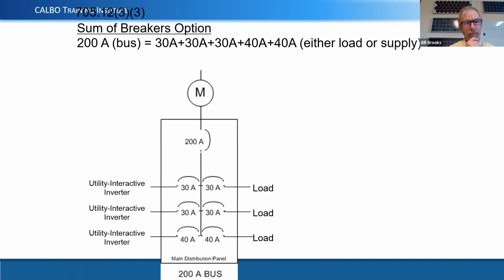Now, it's challenging to do that in most applications, and so normally what we're going to do in an application like this is come off of this panel with another 200 amp breaker. So take all the breakers out of the existing panel, and let's say this is an existing house and they've got 30 breakers in their panel. A lot of these systems, what we're going to do is actually remove all the breakers from the main panel. We're going to put one 200 amp breaker in there and go off of that into other panels, or we're going to put two 100 amp breakers or some combination that adds up to 200 amps. And I'll show you an example of that.